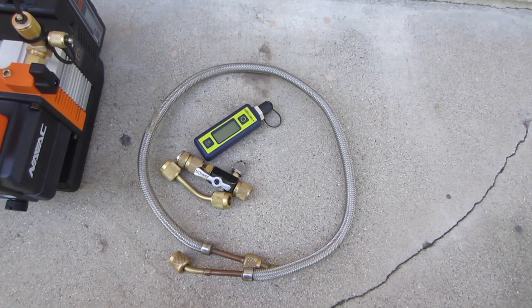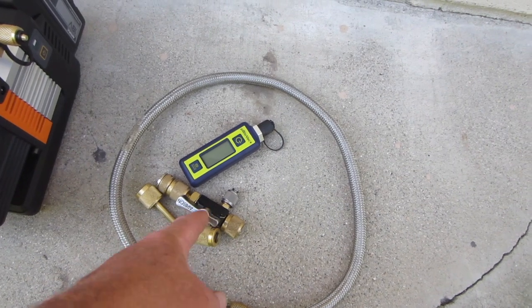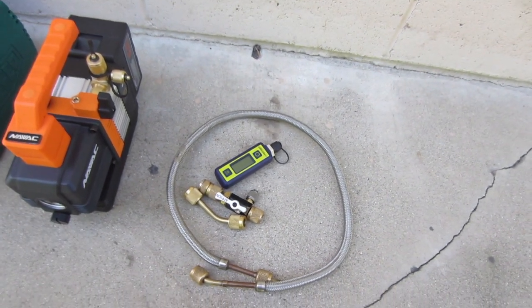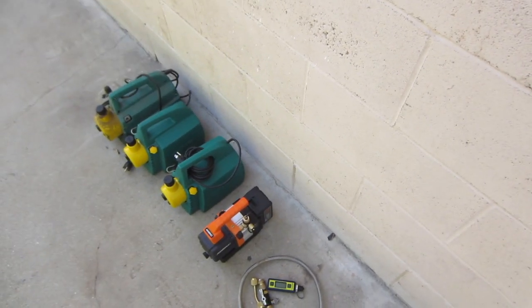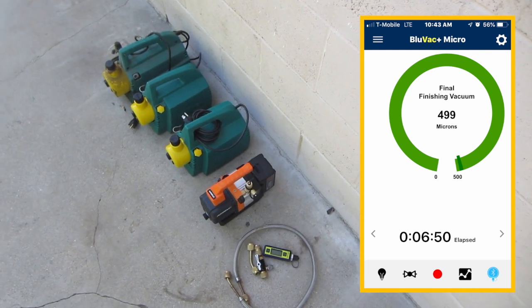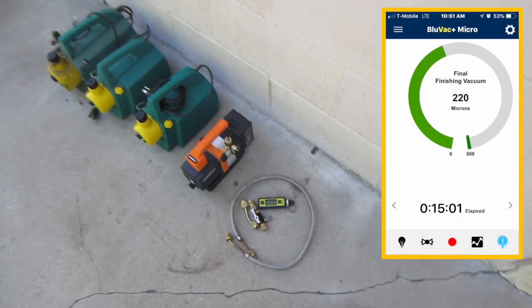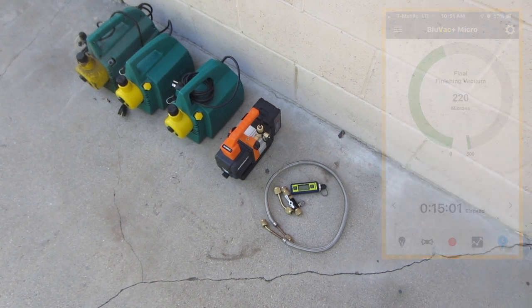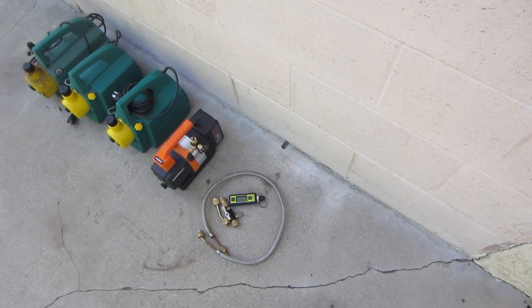This is my vacuum pump setup. I use the Blue Vac with the vacuum coupler, the valve core, the Brad magnet, and one hose. On a new system I'm usually averaging eight to ten minutes to get to 500 microns, and within 15 minutes I can usually get to 200 or 150 — not a problem. I'm excited to see how low I can get with the NAVAC using this setup.